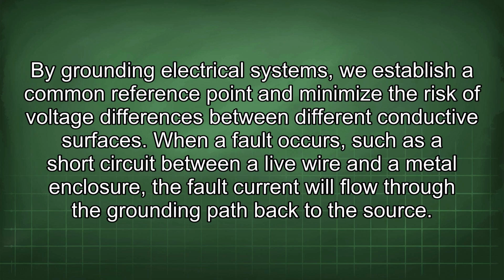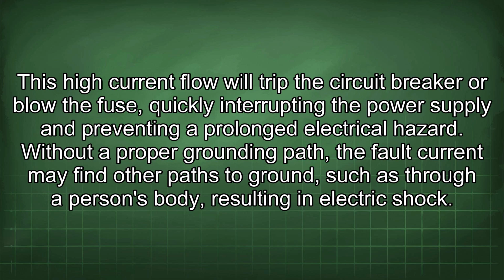surfaces. When a fault occurs, such as a short circuit between a live wire and a metal enclosure, the fault current will flow through the grounding path back to the source. This high current flow will trip the circuit breaker or blow the fuse, quickly interrupting the power supply and preventing a prolonged electrical hazard. Without a proper grounding path, the fault current may find other paths to ground, such as through a person's body, resulting in electric shock.